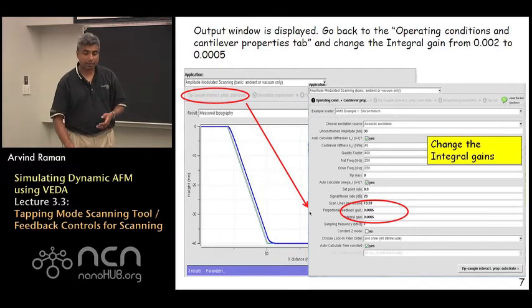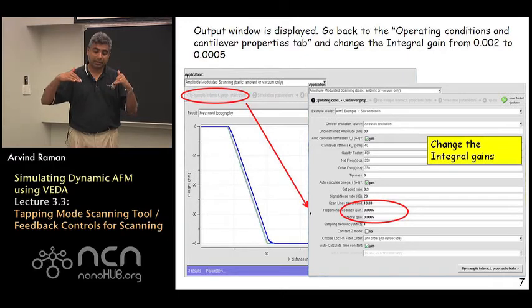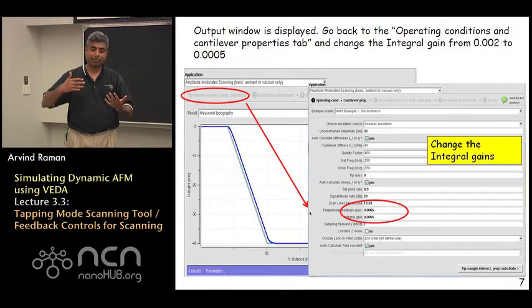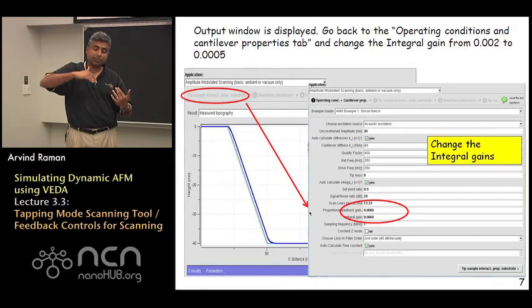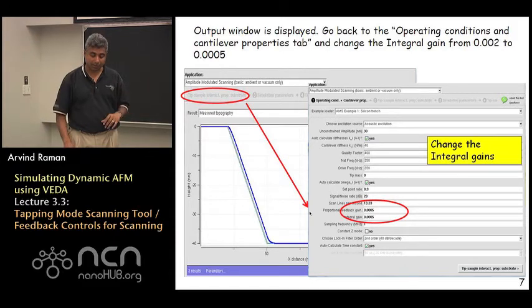Keep in mind that the actual topography is always going to be slightly different from the measured topography by an AFM because all it is doing is moving the base of the lever up and down to keep the amplitude constant.